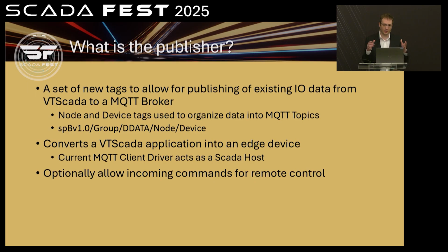The topics are the headers that say this is a data set and this is going to be grouped together. The metrics are the data that's carried within the payload. Not every message has to have every metric in it. You can have sparse metrics sent out. So if only one thing's changed, you only send out that one value. You're not going to send out all 20 if there are 20 different values on that topic. That's why you want to use Sparkplug B, because you can send sparse messages only as needed.